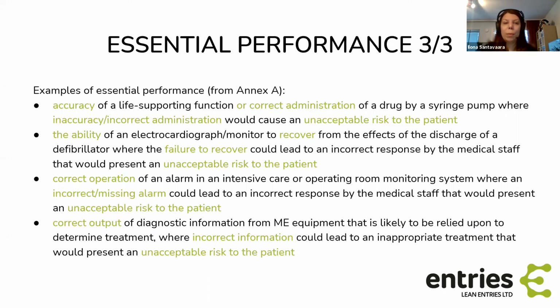It could also be correct operation of an alarm in an intensive care or operating room monitoring system, where incorrect or missing alarm could lead to an incorrect response by the medical staff that would present an unacceptable risk to the patient. So again, correct operation of an alarm could often be essential performance, but only if those devices are in functions like this. So not, of course, if it's an empty battery alarm by a heartbeat monitor that is used for sports or things like that. Although that's kind of a borderline case anyway. Some of those can be medical devices and some cannot.